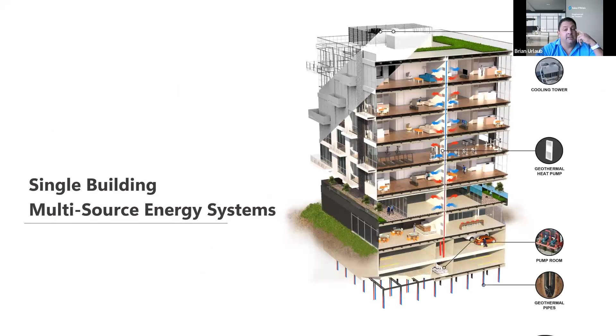A lot of times, depending on that thermal profile, you may or may not need one or both of the hybrid boiler or cooling tower, just depending on what that load profile looks like and what the building envelope is. If you're designing passive house, even in northern climates, oftentimes you're going to be cooling dominant. So do you need that cooling tower as a hybrid peak shaving device?